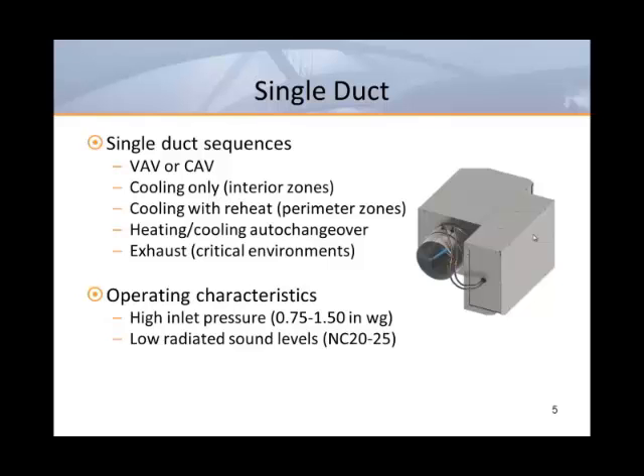Multi-point center averaging sensors are preferred because they can provide improved accuracy with poor inlet conditions. Although single duct boxes have very low pressure requirements, the addition of reheat coils, especially multi-row water coils, can result in inlet pressure requirements as high as 1.5 inches of water.